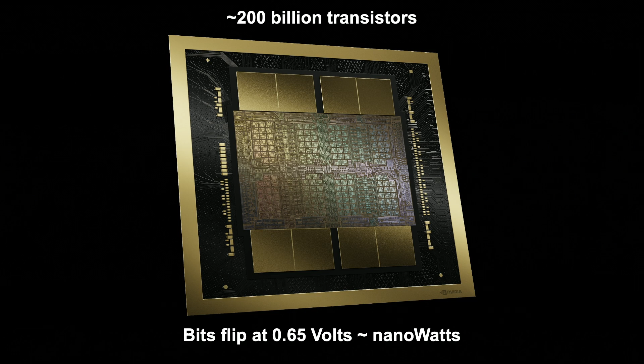Those chips get that power from 48-volt power supplies, and that 48-volt power supply might be connected to a 480-volt AC bus that's also connected to a UPS, or uninterrupted power supply. A UPS can be a backup provision for about 5 to 6 minutes, typically for a large data center. That's a lot of battery systems, but it only can do a few minutes.